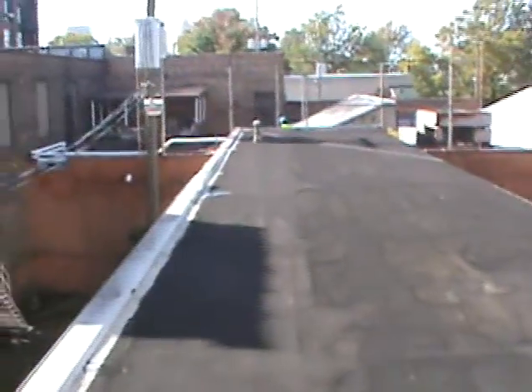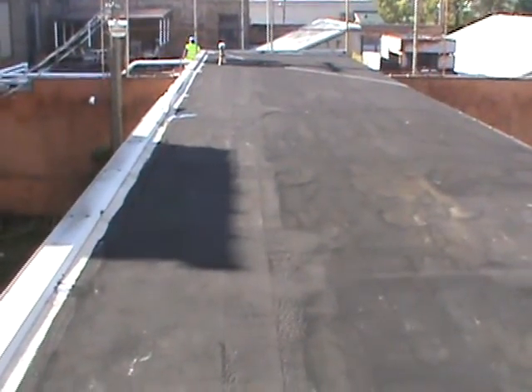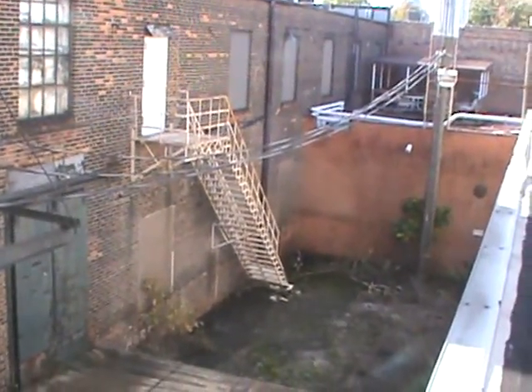This is a pre-existing non-conforming issue that the city official must determine whether or not he wants us to put a catwalk system 8 inches above grade, railings on both sides, feeding the people from here to there to the cantilever, or if he'll allow this ladder to be reversed, a hole to be opened up here, and you go straight down to the ground with the same ladder, but a new ladder completely all the way to the ground. That then feeds that door down there, which is enclosed with a chain that you can open at any time. Single action, requiring no special knowledge. It's the same egress for that stair that's there. That's number one on this inspection that we're doing here.